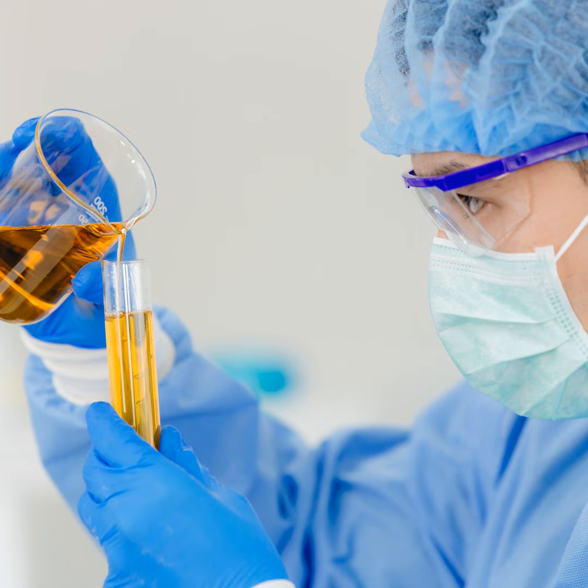One of the strengths of microscopic analysis is that it also allows technicians to visually examine the contamination trapped on the membrane. Comparator charts can then be used to compare the appearance of the contamination with verified reference images, making it easier to estimate the cleanliness classification. Some technicians perform detailed particle counting, while others use these reference images to quickly determine the closest cleanliness class. Both approaches are based on established procedures.